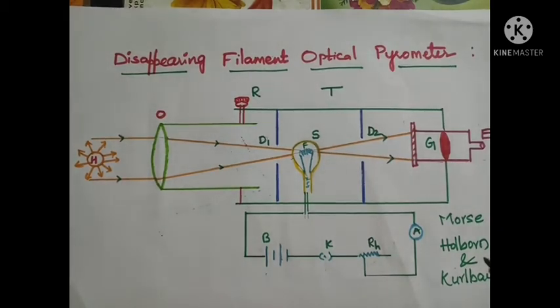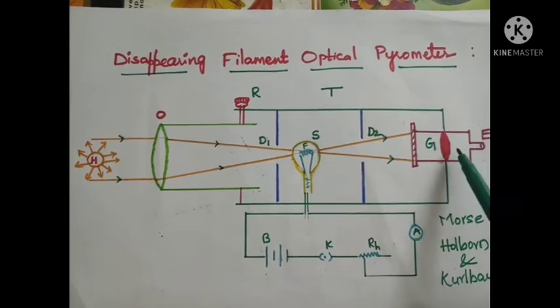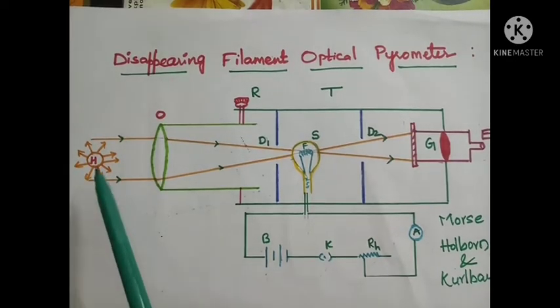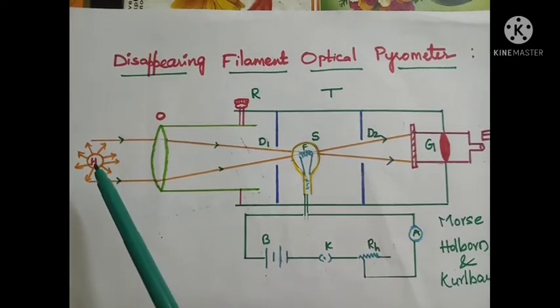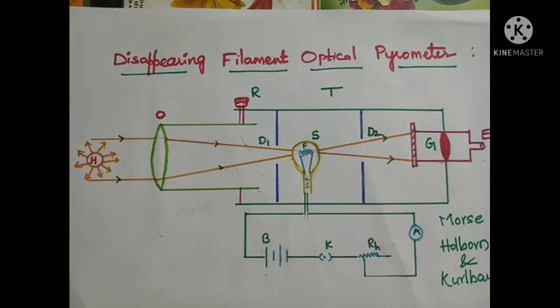With the help of these diaphragms, we can control or limit the rays coming from the source. One more component is a red glass filter G, which is located before the eyepiece, so with the help of this filter we can observe things clearly. The hot body H is placed in front of the objective lens. This is all about the construction of the disappearing filament optical pyrometer.